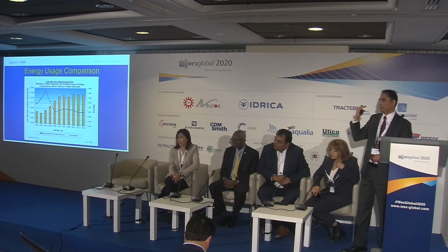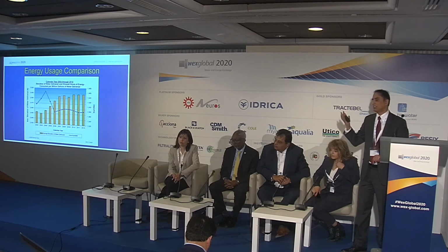And so here's the result. What you see on this graph is that the bars are the average elevation that we pumped water to, and the line is the kilowatt hour per million gallons, the energy that we used. We started sending a daily pumping plan in July 2005, and you can see that within 6 months we saw the benefit. By the time we did the whole year in 2006, we saved 15% in energy.